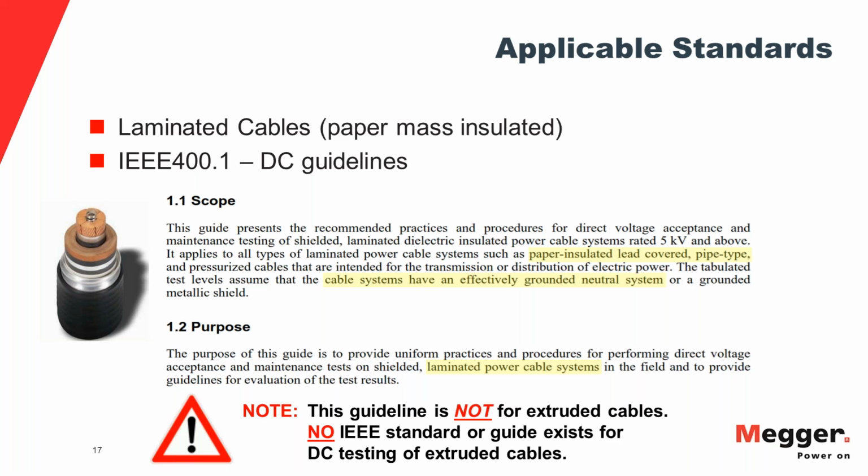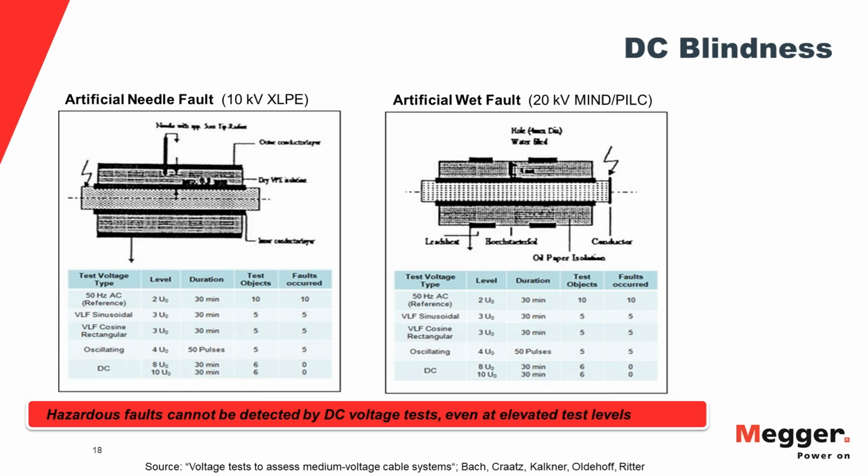I mean, we're talking about a good 10, 15 years now since DC testing is banned in North America, and even longer in the IEC world. So DC testing is still okay on PILC cables, even if I would still do a VLF on the laminated cables as well, and definitely don't do DC testing anymore on solid dielectric cables. And then there's another thing on top of that, a result of the DC test damaging the insulation, which is, by the way, called the space charge effect.